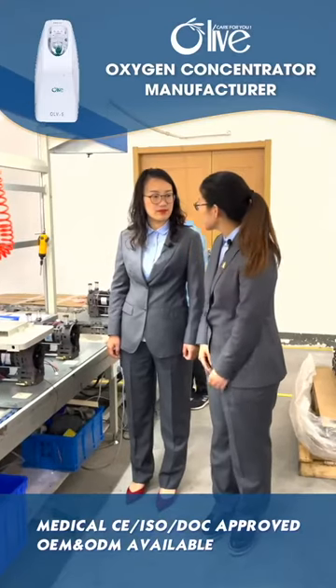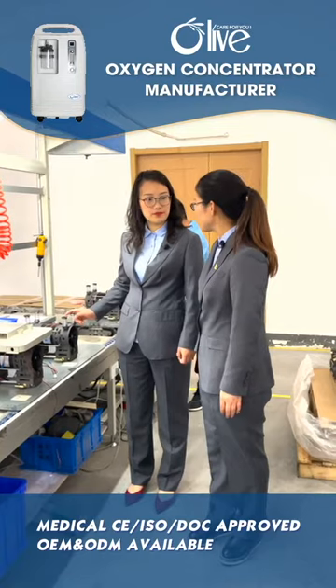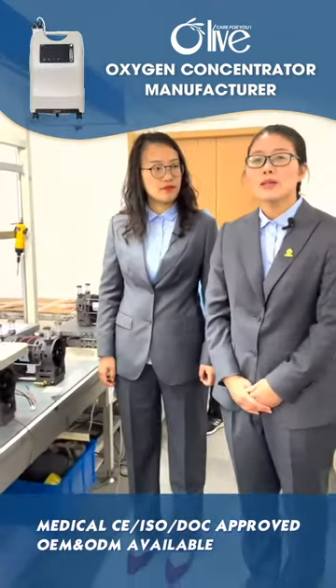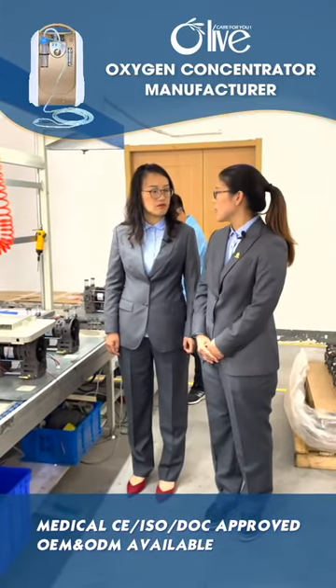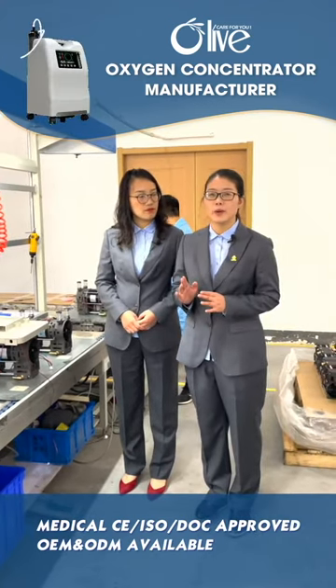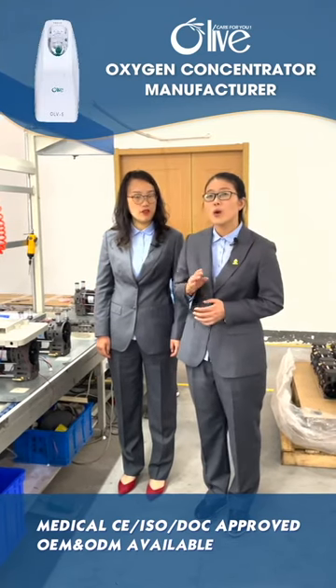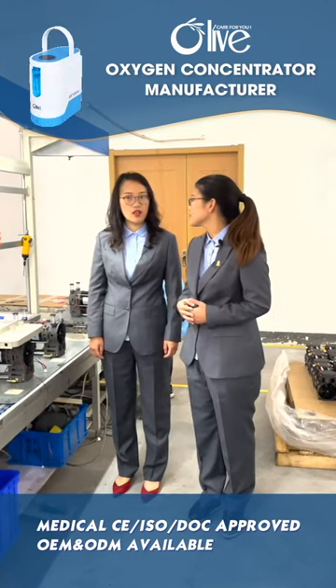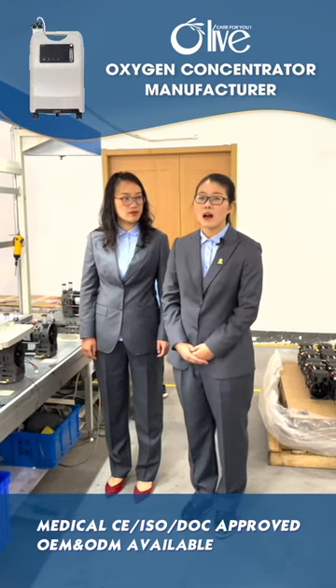Hi, Grace. I'd like to introduce you to the first assembling step of our oxygen concentrator. You can see this is our air compressor. As you know, the air compressor is one of the most important components for the oxygen concentrator. Inside the air compressor, there is one cap, which is very important. We import this air compressor cap from Japan.